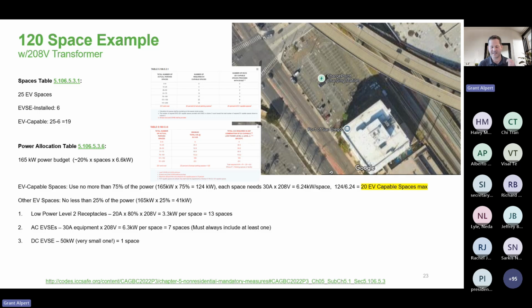And then on the other side, there's the no less than 25% of the power that has to be a low power level 2 receptacle, or regular level 2 receptacle, or DC fast charger. So if we're looking at low power level 2, that's 20 amps times 80% duty cycle times 208 volts, and that's 13 spaces that are low power level 2 receptacles. If it's AC, 30 amp equipment, so slightly more than 20, but still pretty low, that gets 6.3 kilowatts per space. And so there has to be 7 spaces that are AC EVSEs.